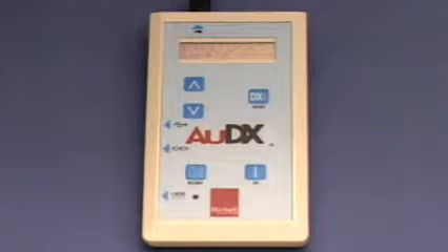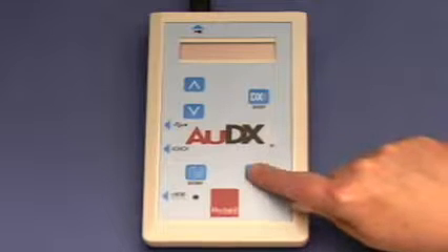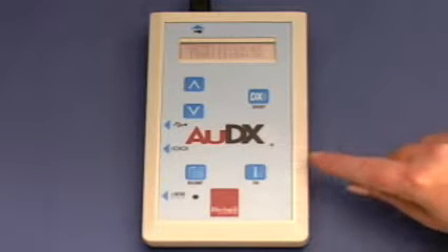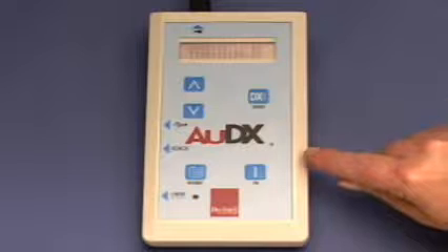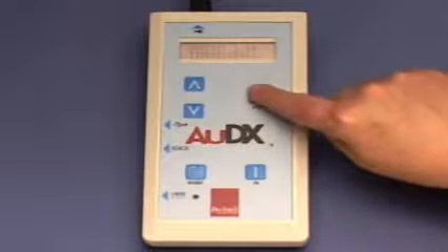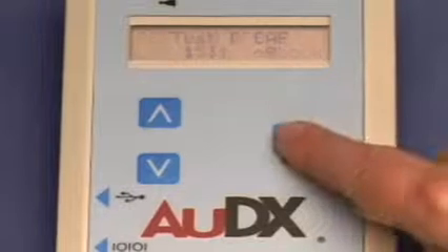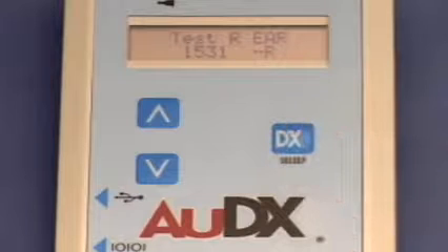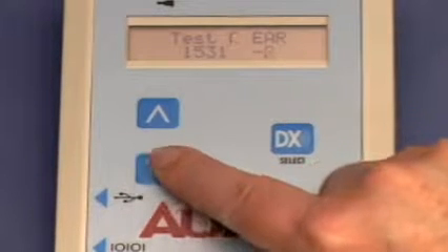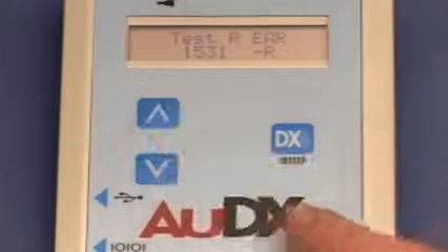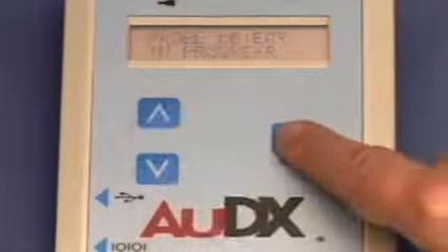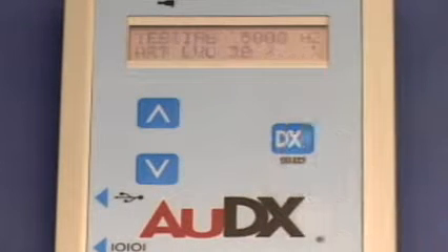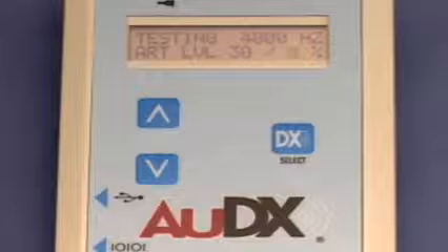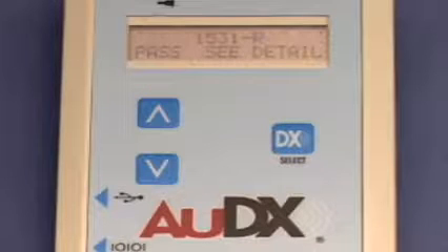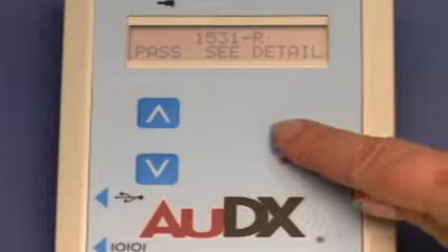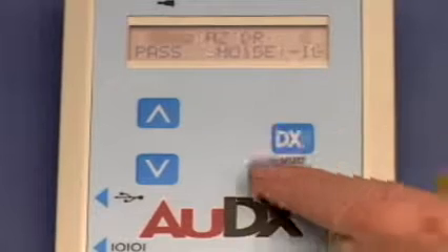Now, let's quickly review. Press the On button, then press DX to enter the program. Press DX to go to the ear selection screen. Select the ear you want to test, then press DX again. After checking the probe fit and calibrating, AuDX will perform the test and display a pass or refer message. Press DX again to display details of the results.